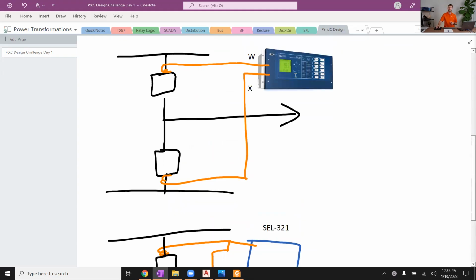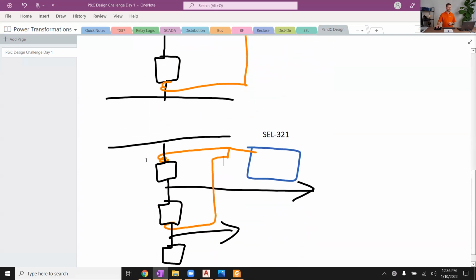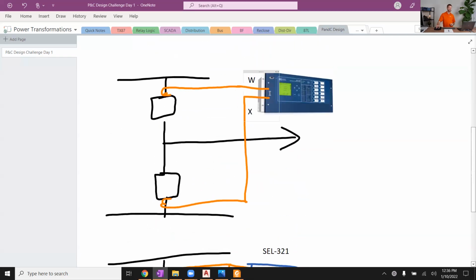And some of those advantages, like Sean pointed out, these could be separate CT ratios, and the relay can calculate and normalize the two to one another with math equations, versus when they're summed together external to the relay. This is how it was done in the electromechanical days as well. The CT ratios must match. We're going to go into more on what is a CT ratio if you don't follow that discussion. But then other added value capabilities of doing them separately.